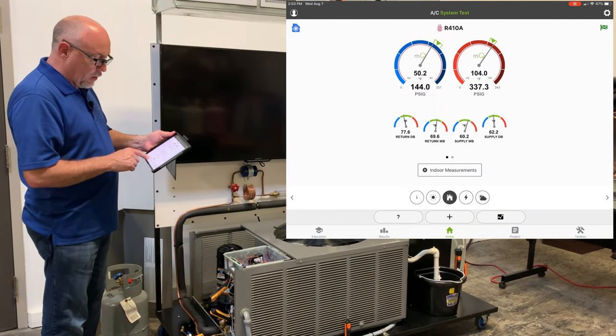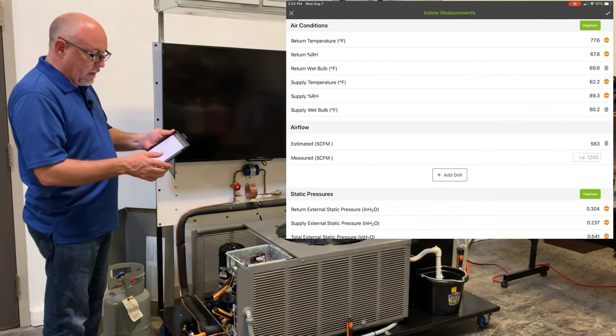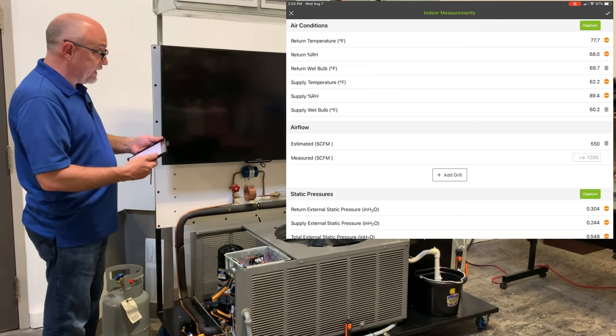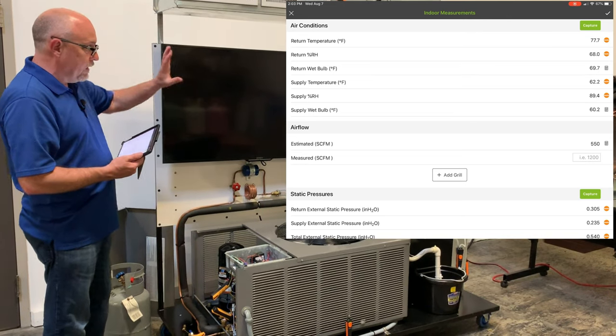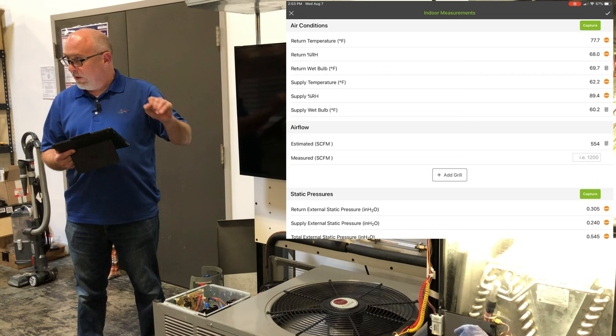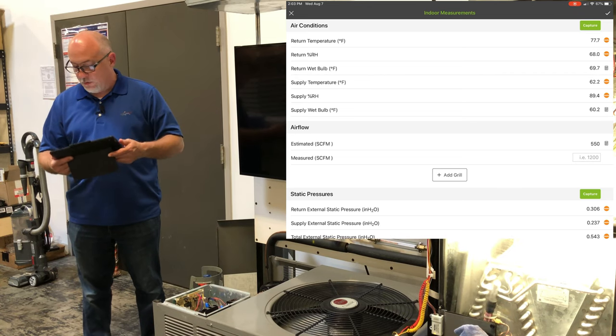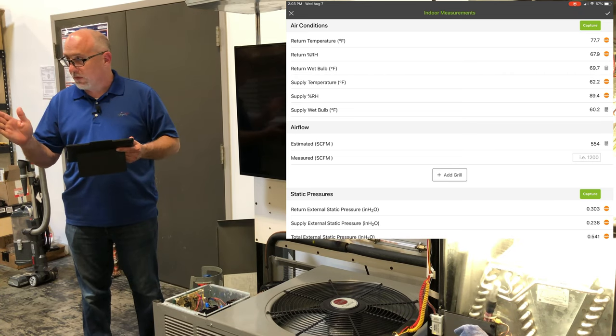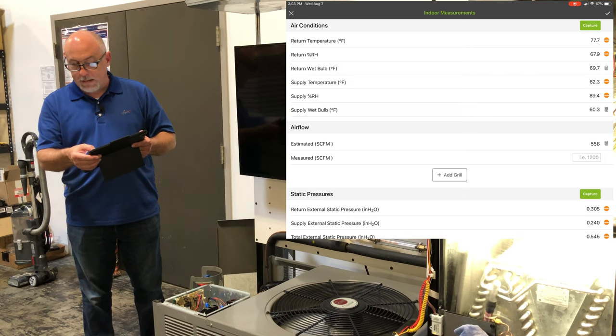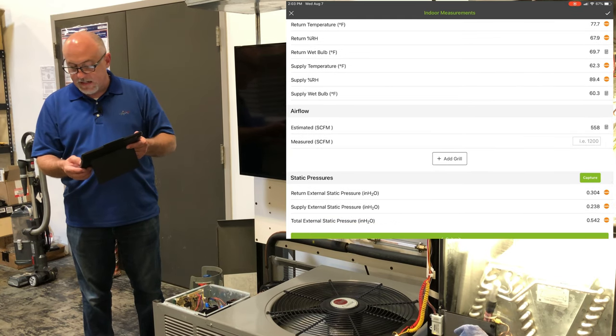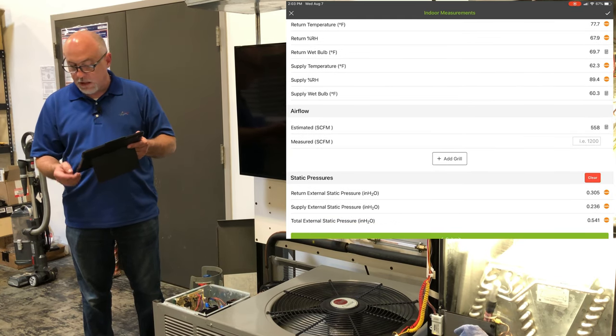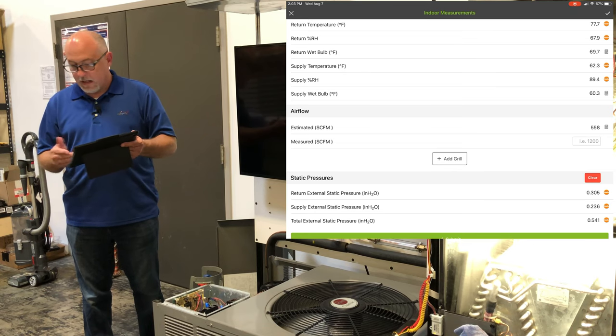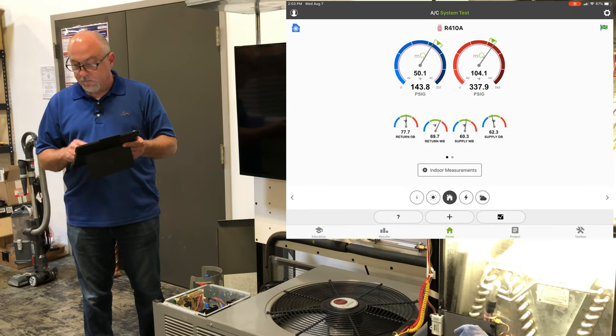Indoor readings on here, same thing. But I want you to notice there, in this case here we have a mix of the old and new testo probes. We know that the older testo probes didn't have great range. Well we have a solution for that in MeasureQuick. Again there's a capture button here and a clear button, so if I want to go inside and capture those static pressures and lock those readings in, I can do that on MeasureQuick and hit submit.